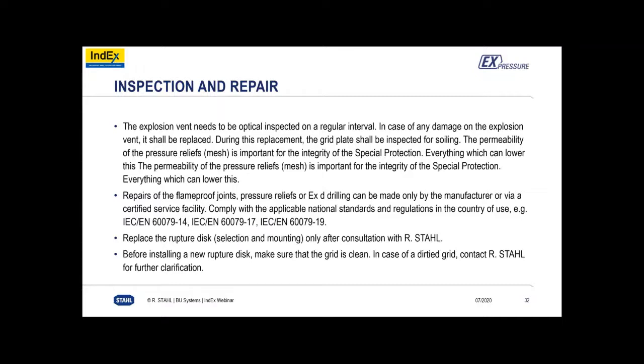Okay, so any repairs of flameproof joints, of pressure relief, or for drilling of new entries, let's say, must be done by the manufacturer, Stahl, or an approved IECEx service facility. I would still speak to the manufacturer, and if you can't get it back to Stahl, ask them for who they approve, which IECEx service facility, which you can find on the IECEx website. So you must comply with the certificates, with the IOMs, and the standards, and any national deviations.